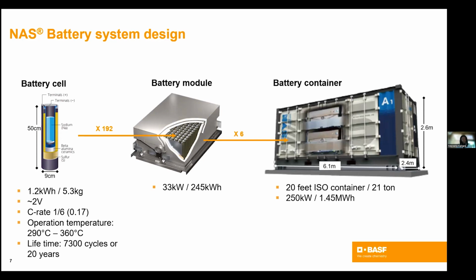It contains sodium, sulfur, and a beta alumina ceramic. There are 192 of these cells put into a battery module. That module is about 2 tons, and 6 battery modules enter into a container, so it's already a containerized system with minimal fixing needed on site. The container is 21 tons, and one container, a 20-foot container, is 250 kilowatt, 1.5 megawatt hour.